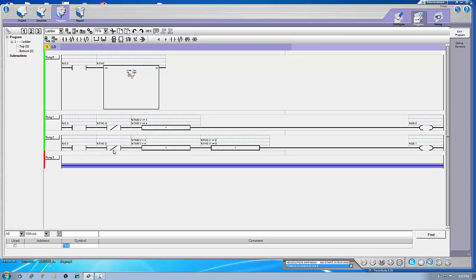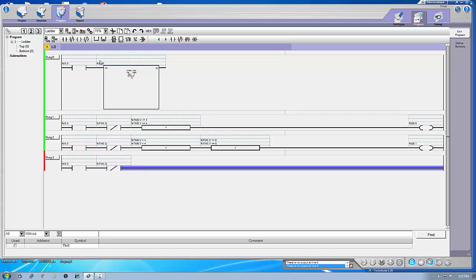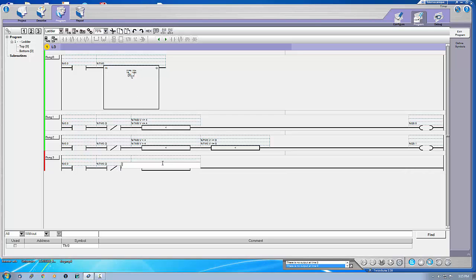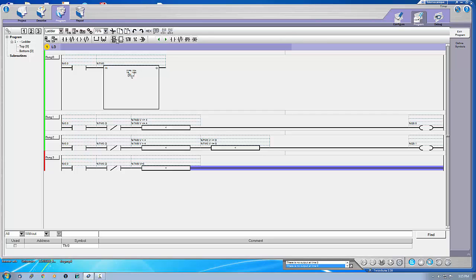Now the demonstration was about three outputs and one input — two are done, now the last one. Just make another TD bit — the same TD bit, everything is the same. Now another compare block: the accumulation should be greater than eight but less than or equal to 12. Output Q:0.2. That's it!